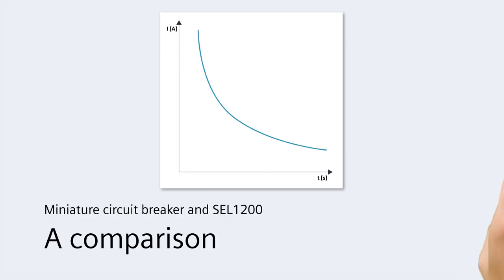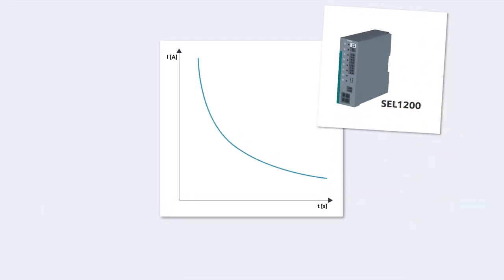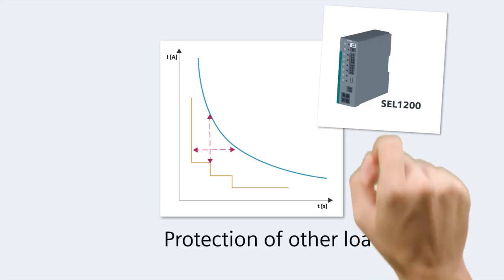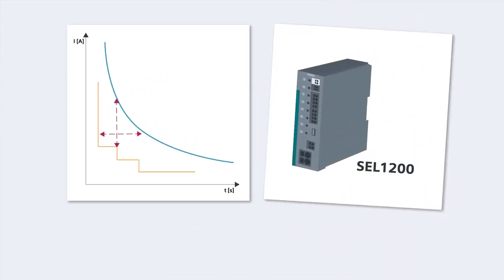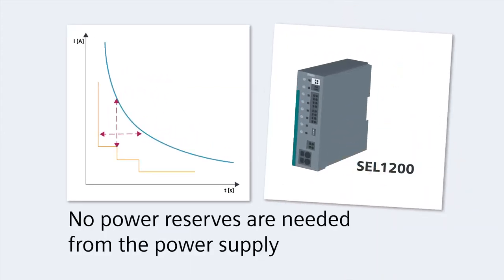Let's take a look at the SEL1200. As you can see, when a fault occurs, the SEL1200 trips much sooner. It also responds to a much lower current, meaning that the other loads are much less affected and the voltage dip is minimized. And because the switching characteristic of the SEL1200 means it is optimally adapted to the switched-mode power supply, no additional power reserves are needed.